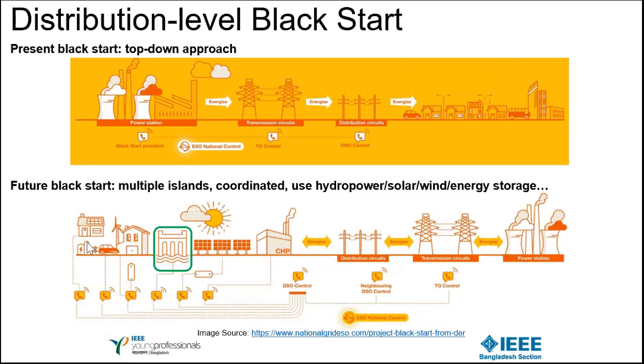So they have to adjust the protection settings for traditional black start as well. But with distribution level black start, we can leverage the fact that we know there is a blackout, the transmission system is not live yet, and the bulk power plants are just starting to restart. Why don't we use our distribution level resources, say solar and wind, and maybe some storage, so they can start reconnecting to the grid and re-energize the distribution level, and wait for an interconnection request from the live transmission system to reconnect?